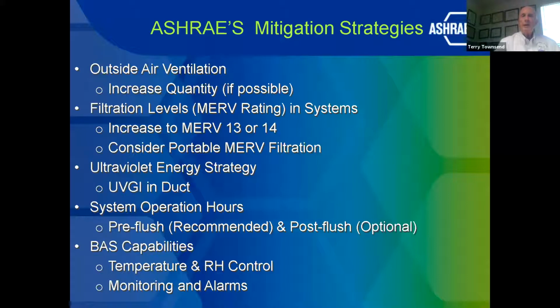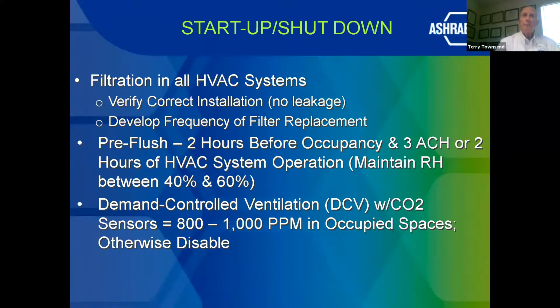But the BAS, building automation system capabilities, are for temperature and relative humidity controls, as well as monitoring and alarms. So what we want to do is filtration on all HVAC systems, and we want to make sure the filters are installed correctly so there's no leakage. Because if they're not installed correctly, especially if you're upgrading, you can get a 15+% bypass. And so what this creates is an ineffective filtration system. And then make sure you have a frequency of filter replacement.